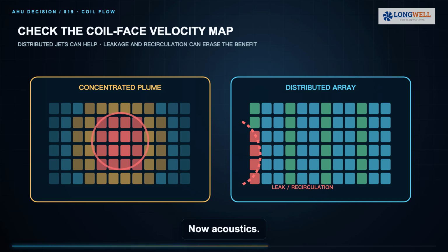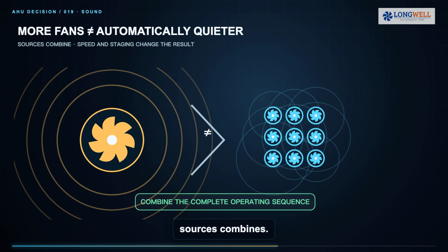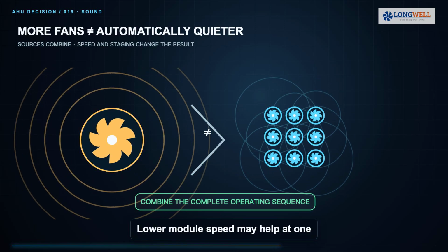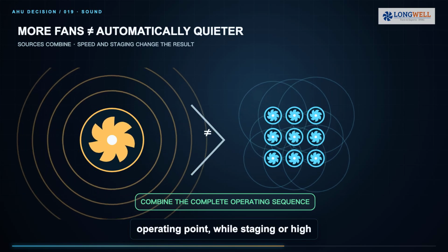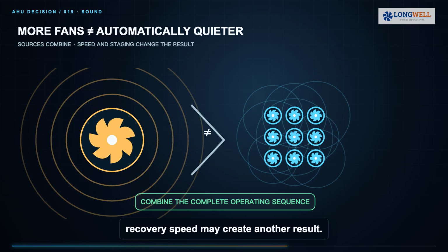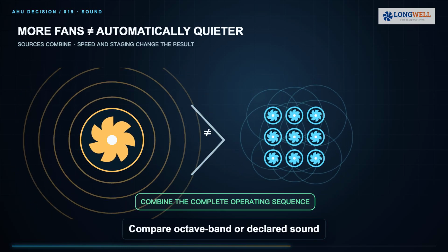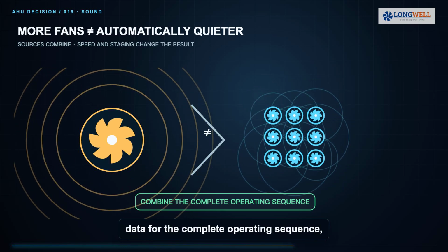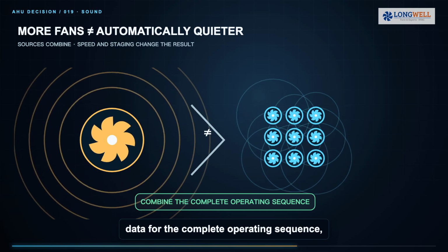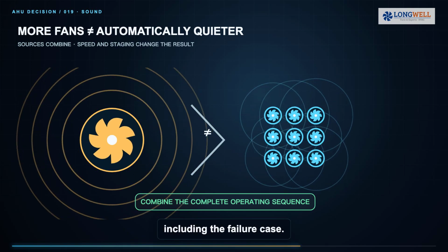Now acoustics. More small fans are not automatically quieter, because sound from multiple sources combines. Lower module speed may help at one operating point, while staging or high recovery speed may create another result. Compare octave band or declared sound data for the complete operating sequence, including the failure case.